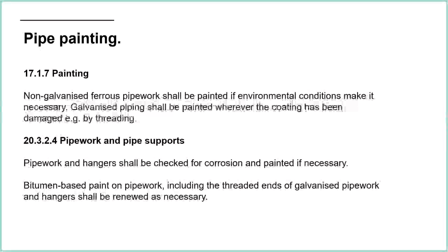The actual sprinkler pipework itself is generally painted in red oxide. It's like a primer, to be honest. But that's normally what's done: this red oxide paint coating on the outside, and then it's just left alone. So we normally have red. Seems to make sense to me: fire, red. But there's no requirement for it to be red. It can be a different colour. I know we did some work at Canary Wharf, and the sprinkler pipes in Canary Wharf are grey. So grey or red seem to be common colours to be used.